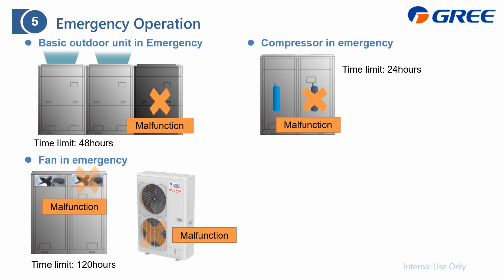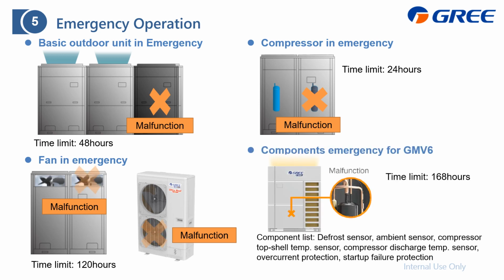Also, we have this for the fans. The time limit is 120 hours. And when you exceed the time limit, the system will display AD. That means your time has expired. And we do not recommend resetting the power to get another time limit. This is for GMV 5, also for GMV 4, for GMV 6. For GMV 6, there's also additional component emergency, which means we can shield the components. For example, if the compressor discharge temperature sensor is malfunctioning, and due to this the system cannot operate, this emergency operation lets it keep running.